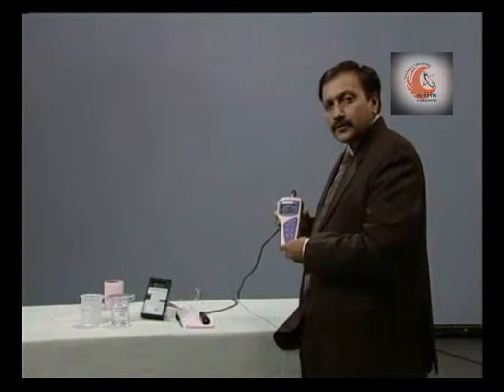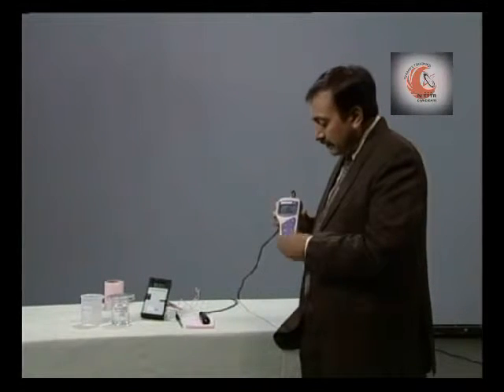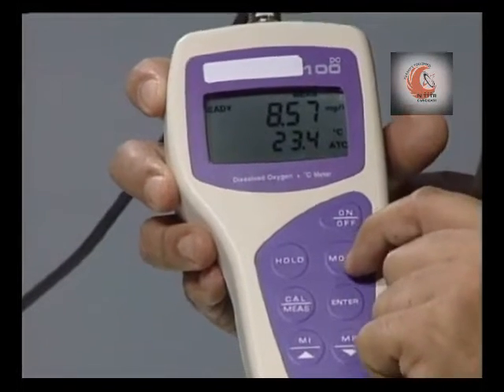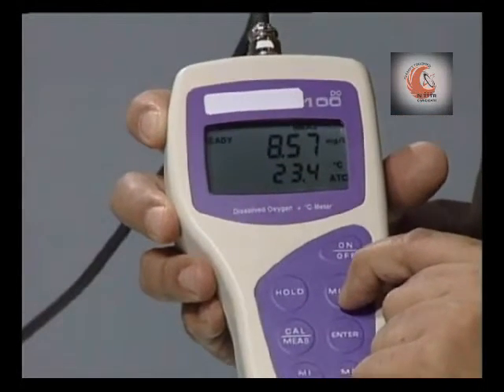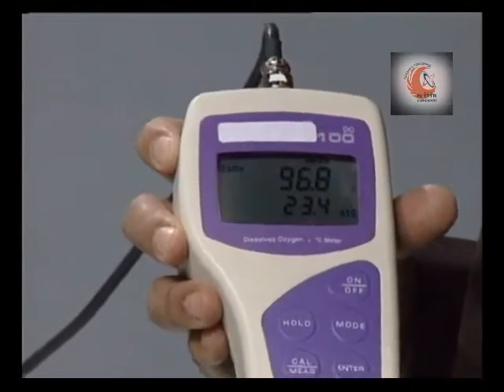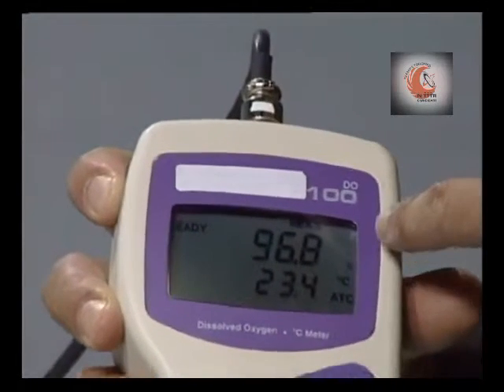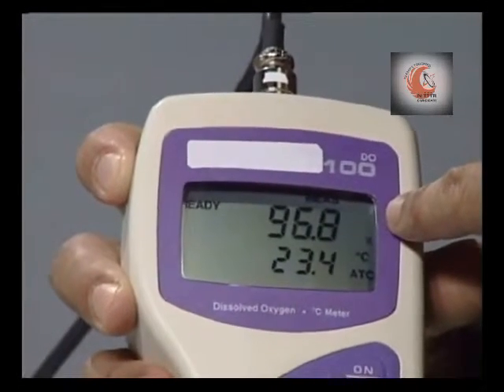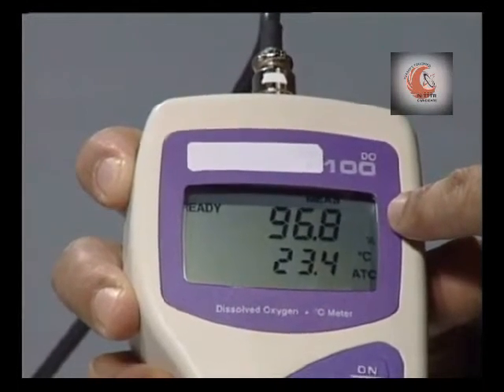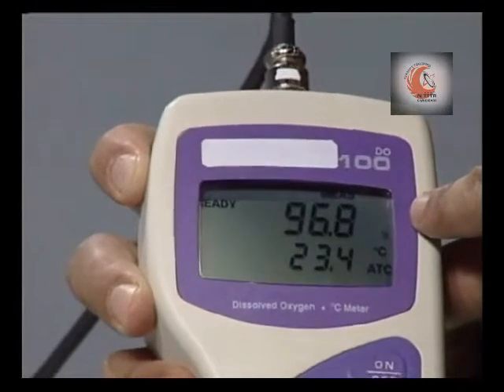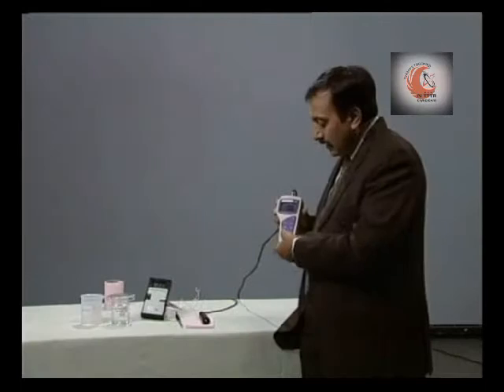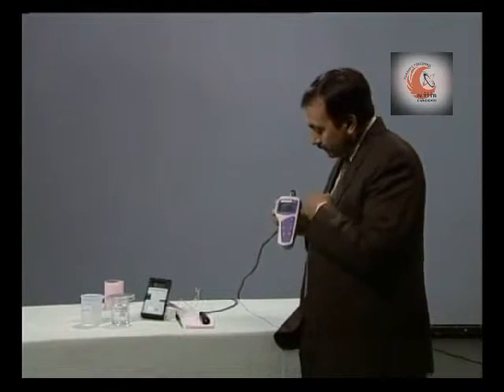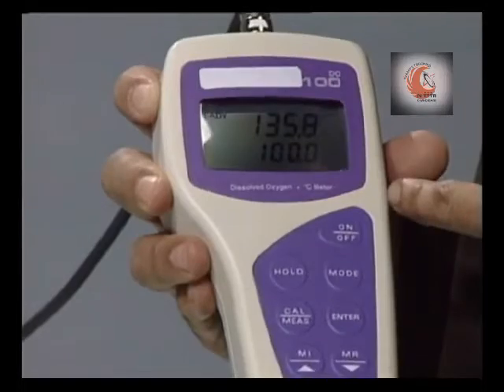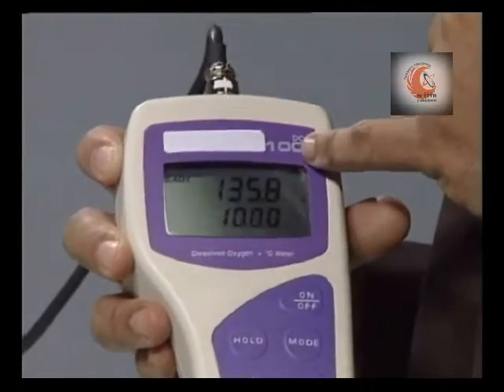Now we have to carry out the calibration for percent mode. So first we will bring the instrument in percent mode. Now when the percent is displayed, that confirms that the instrument is in percent saturation mode. Now press the cal switch. Now the instrument is in calibration mode.